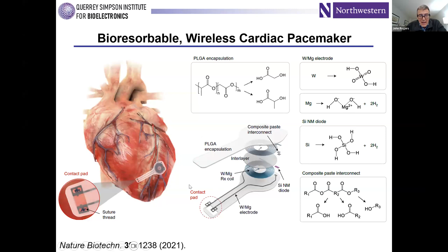And I won't go through the details, but we've been able to put together a device that satisfies all of those requirements. So it's a pair of pacing leads that we construct out of a combination of tungsten and magnesium, both bioresorbable metals. Those are coupled to a pair of inductive coils that serve as a basis for harvesting wireless power from an external transmission coil. That harvested power comes in as an AC waveform that we rectify with a silicon nanomembrane RF diode. Silicon itself is bioresorbable. And then we use polymers that are known to be biocompatible and bioresorbable as encapsulation layers and as substrates. So it turns out to be a thin device that you can just affix to the epicardial surface, and then you can wirelessly activate pacing on an as-needed basis.